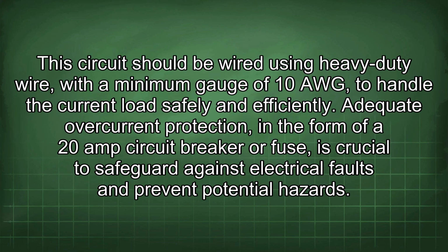This circuit should be wired using heavy-duty wire with a minimum gauge of 10 AWG to handle the current load safely and efficiently. Adequate overcurrent protection in the form of a 20 amp circuit breaker or fuse is crucial to safeguard against electrical faults and prevent potential hazards.